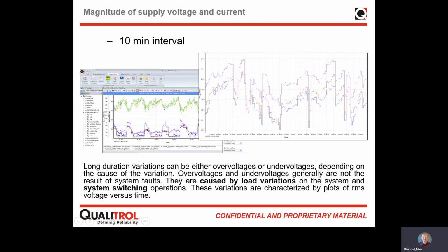And what we see here is the currents in the evening, it's dropping off, and then in the morning around 8 o'clock, people are coming into the office and the current and the load is increasing. So it increases over the course of the day, in the afternoon and the evening starts to tail off again, and then at night time. So that's potentially Monday, Tuesday, Wednesday, Thursday.